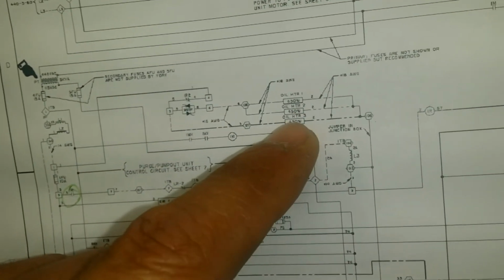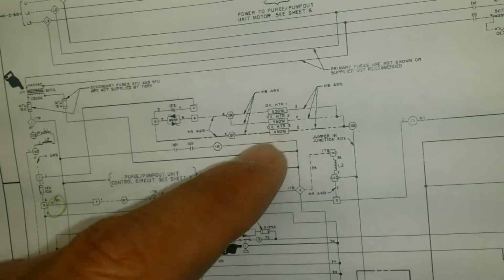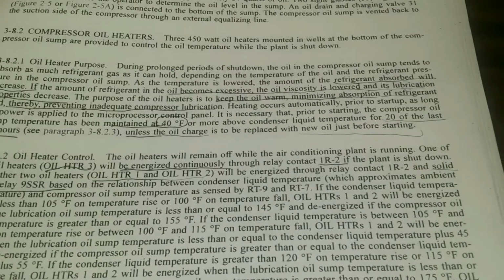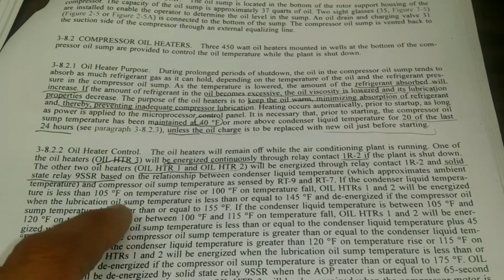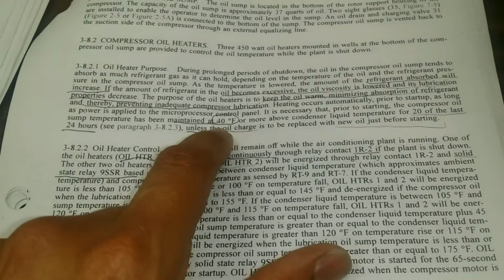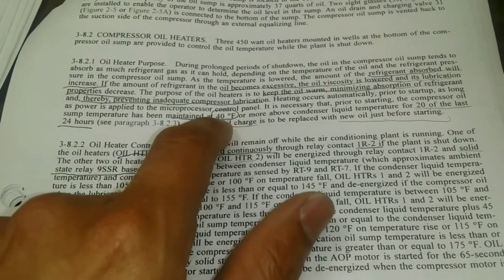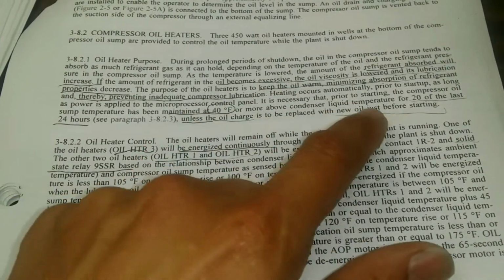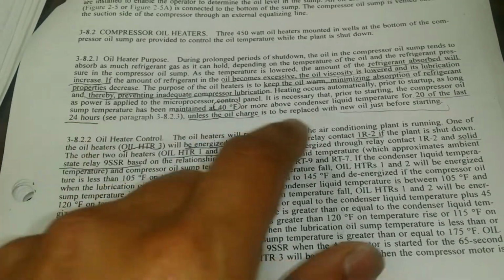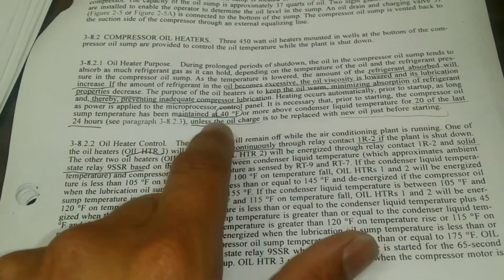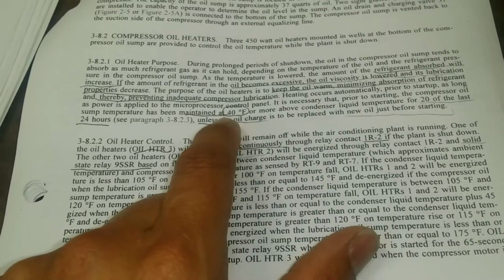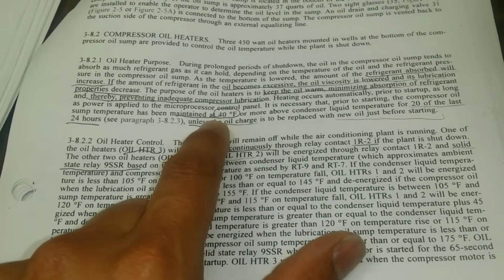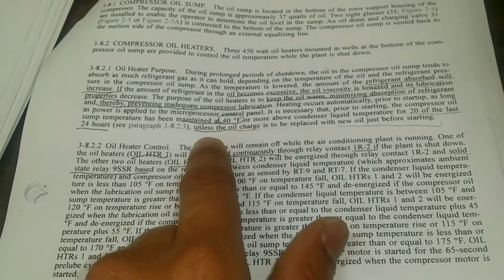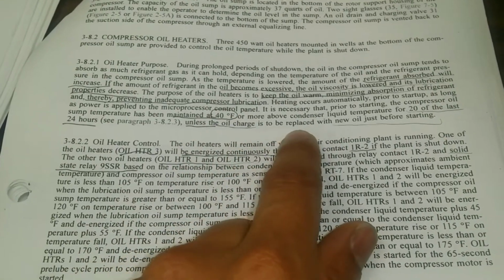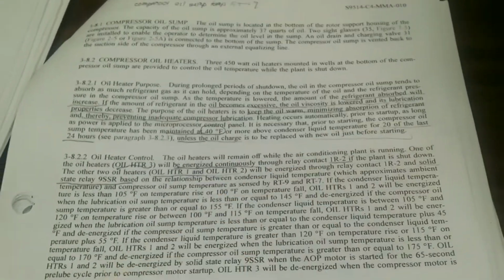Now, it is important to keep the oil temperature above 40 degrees so that refrigerant does not mix with the oil. When that happens, the oil loses the ability to lubricate the compressor. I also want to share this statement over here that says, within the last 24 hours, 20 of those hours, the oil has to be above 40 degrees before you start the AC. The only exception to the rule is if the oil was recently replaced.